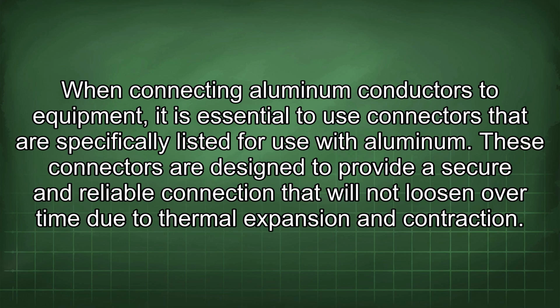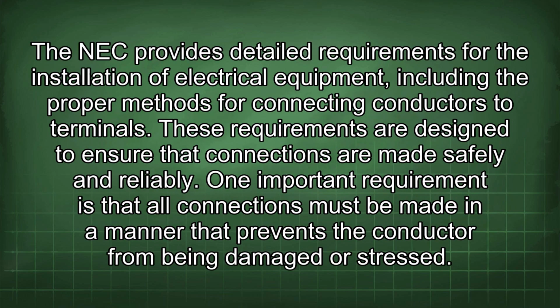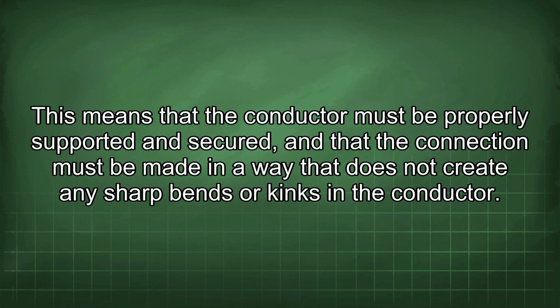expansion and contraction. The NEC provides detailed requirements for the installation of electrical equipment, including the proper methods for connecting conductors to terminals. These requirements are designed to ensure that connections are made safely and reliably. One important requirement is that all connections must be made in a manner that prevents the conductor from being damaged or stressed. This means that the conductor must be properly supported and secured, and that the connection must be made in a way that does not create any sharp bends or kinks in the conductor.